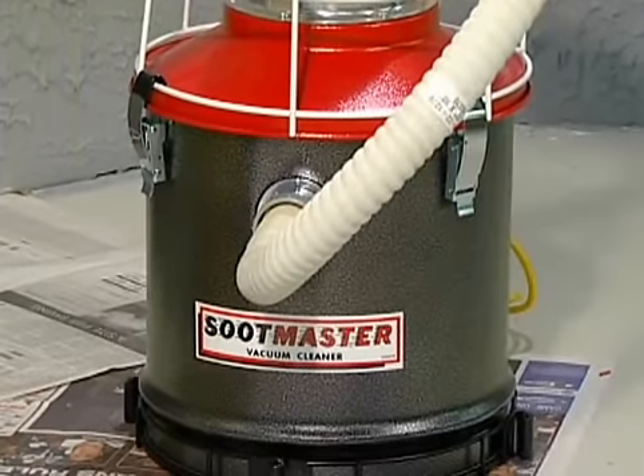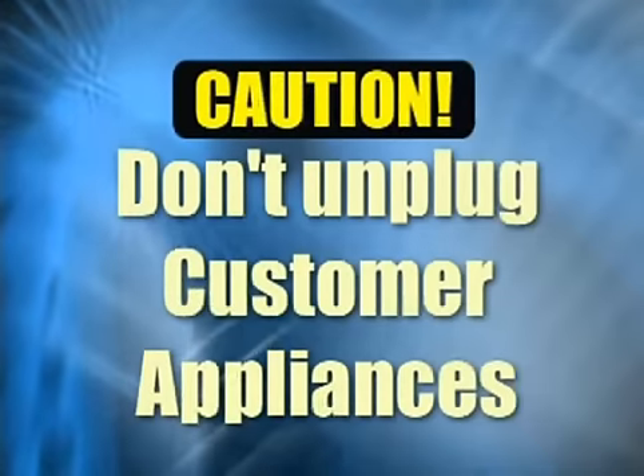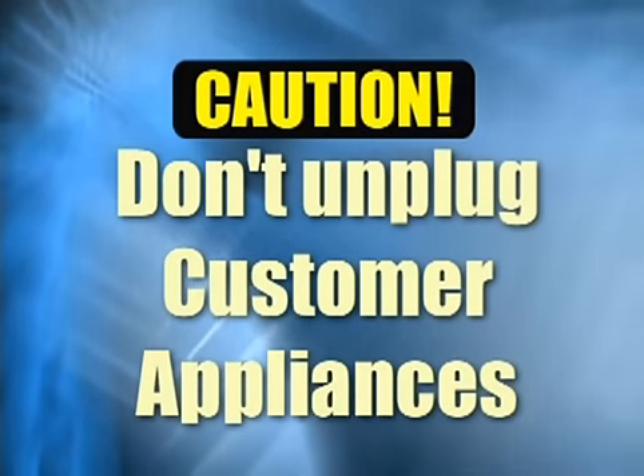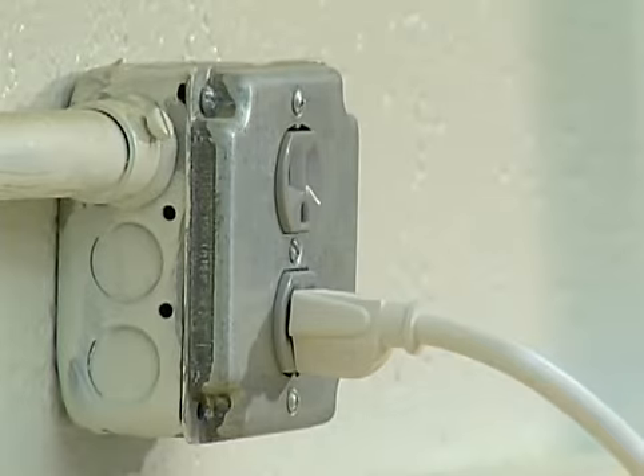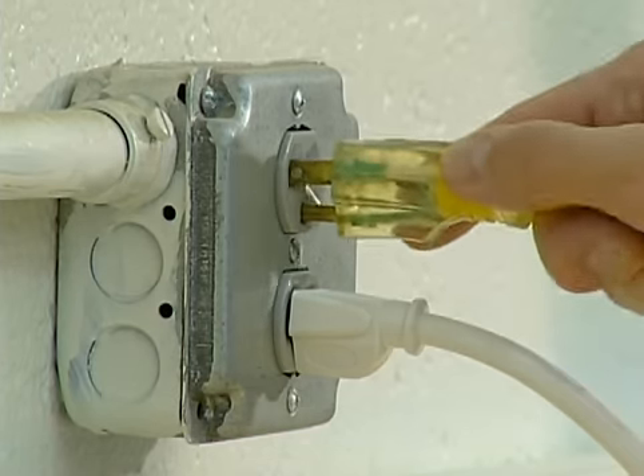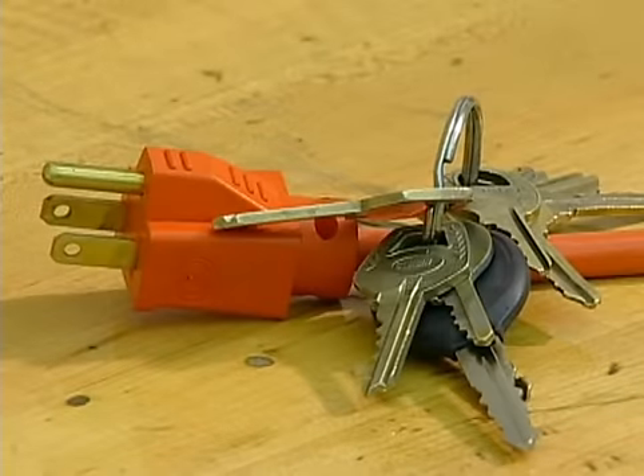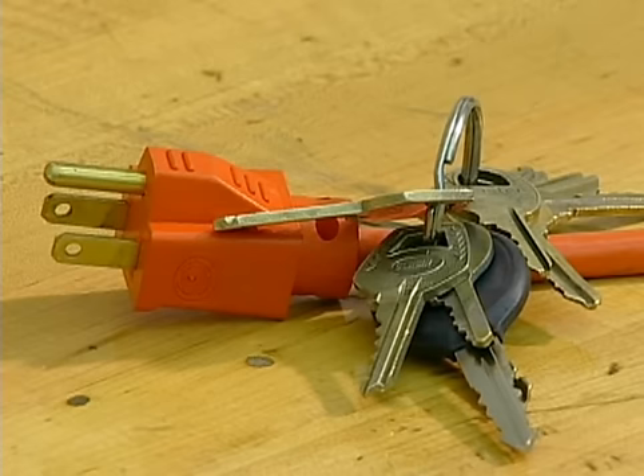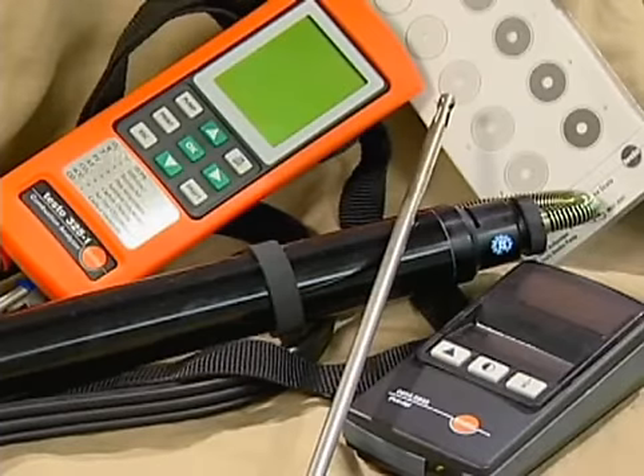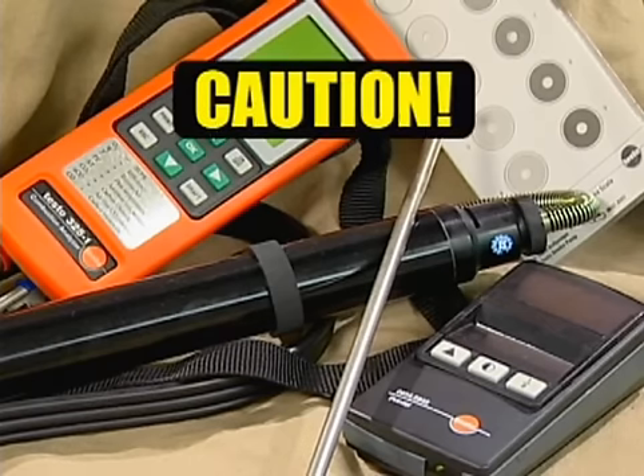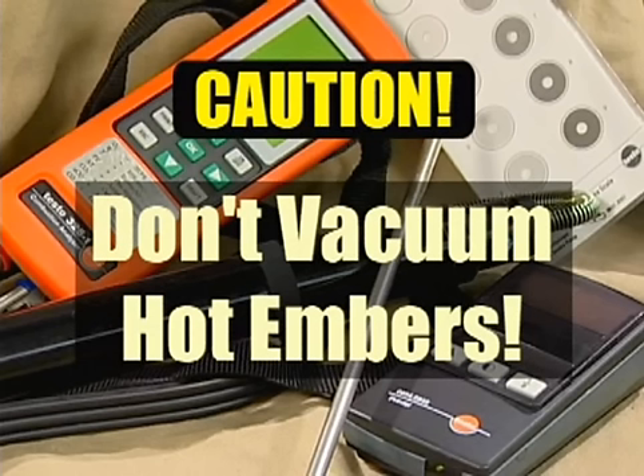When you plug in your vacuum or any power tools, be careful not to unplug any appliances. If anything has to be unplugged, attach your truck keys to the cord to remind yourself to plug it back in before leaving. If you performed a quick-fire test or if the burner was operating when you arrived, be extremely careful when vacuuming the unit. Don't allow any hot embers to get sucked into your vacuum cleaner, as they may ignite the filter and cause soot damage in the house.